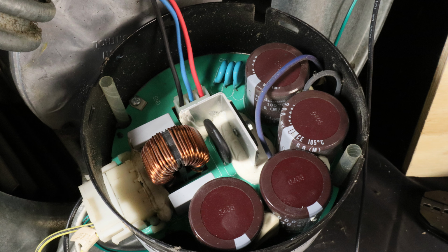Now, the reason why we turn it from AC to DC is so we can clean it up. And then when we turn it from DC back to AC, we can control those AC signals by modulating the DC voltage. So when we turn that DC voltage up, all 3 of those AC signals get stronger. We create bigger magnetic fields, and the motor runs at a higher speed. So we can adjust it by modulating that DC voltage as the logic plays out. And those 3 individual AC signals get sent to each winding on the motor, 3 windings, and that's the 3 wires we see here. These 3 blue discs we see over here, those are surge protectors. It's just another level of safety to protect the circuit.